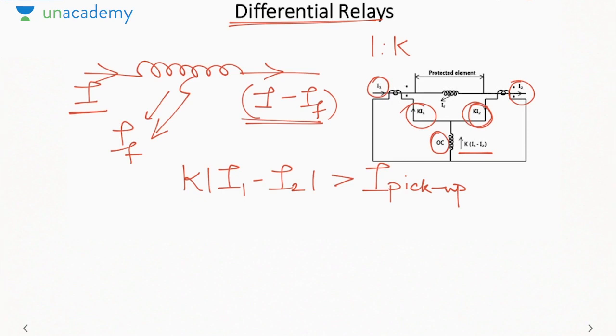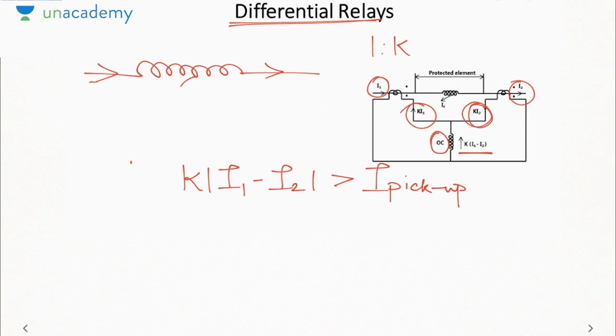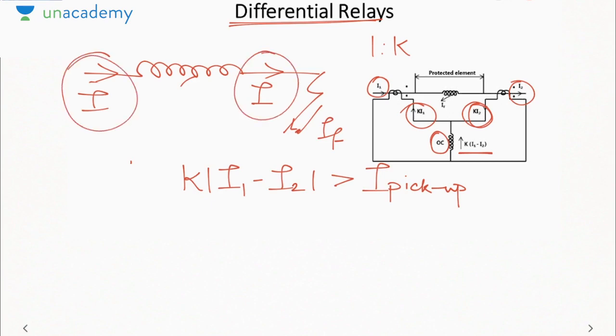But the problem is that it can only operate for an internal fault, that is, a fault between the two ends of the coil. Now suppose the fault was occurring outside; then the current I here will be I, and the current here will also be I. If you compare these two currents, both are I, which means the relay will not be able to detect any type of fault. So the fault must occur between the two ends of the line so that the currents do not match at both ends and the differential relay can operate.